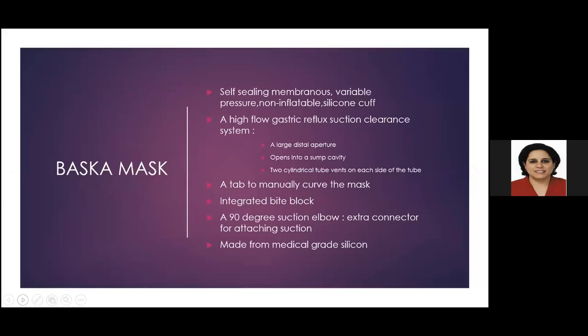There is a high flow gastric reflux suction clearance system, in the sense that the distal aperture is comparatively very large. It has two cylindrical tubes that lead from that sump cavity on each side of the tube. One can be left open to equate the pressures with the atmosphere. The other has a 90-degree elbow, which can be intermittently connected with a suction. There is a tab on the mask to change the curve of the airway to make the insertion easier. It has an integrated bite block.